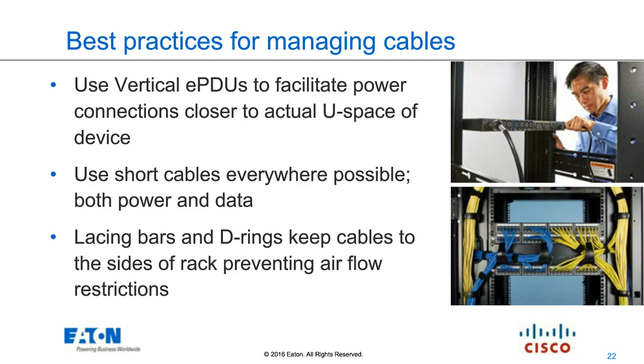To that point, purchase short cables. Most IT equipment comes with 6 or 8 foot cables, but if you're building your rack properly, you don't need cables that long. That's designed to reach something close by. If you invest in a power distribution rack in the back, you can use much shorter cables—1 or 2 feet is usually plenty.